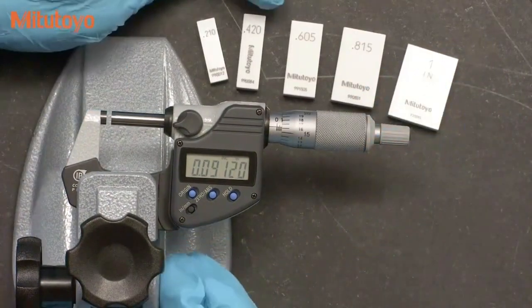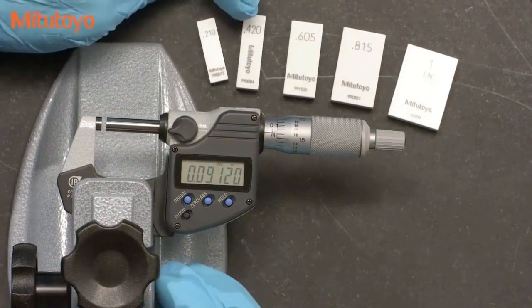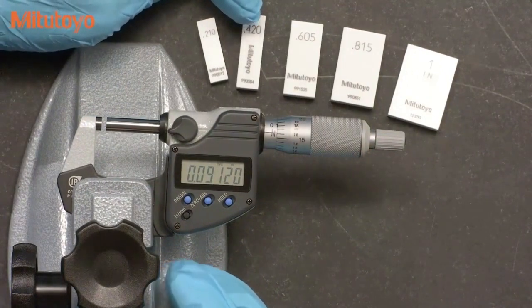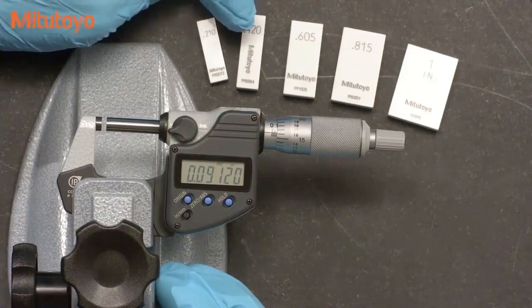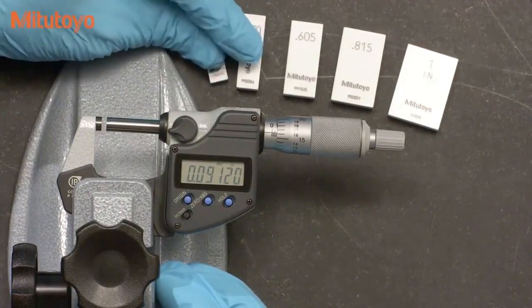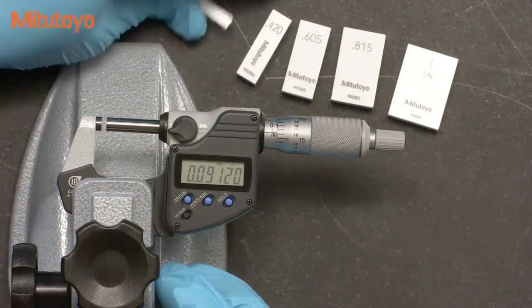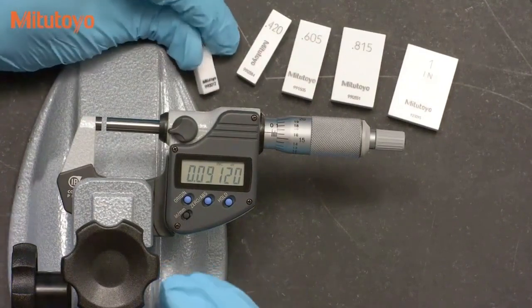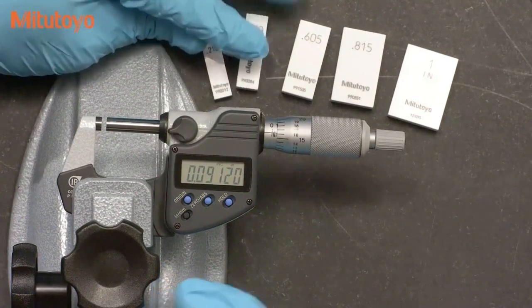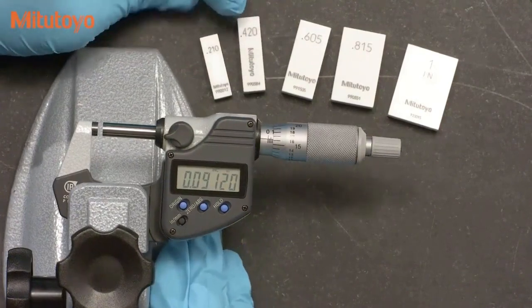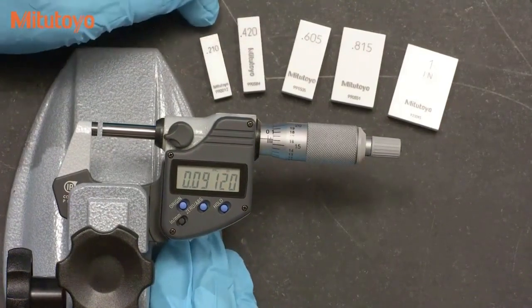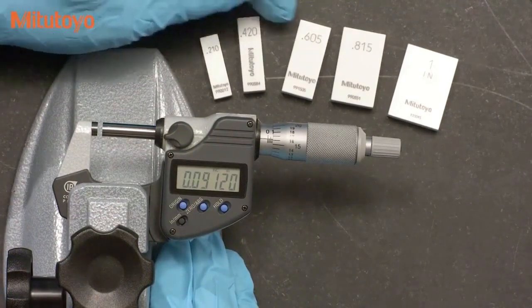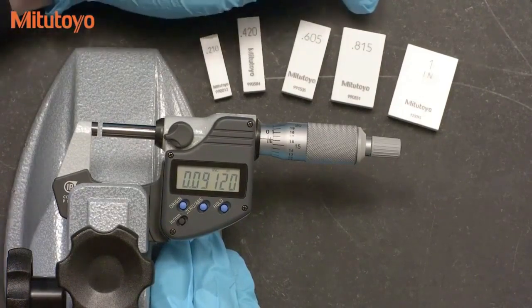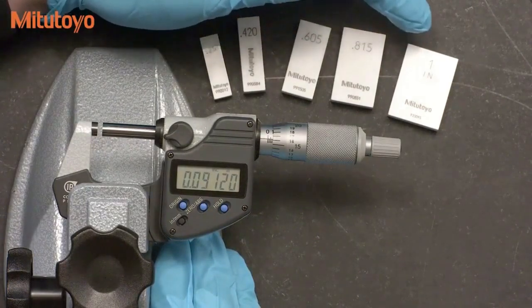We recommend the use of gauge blocks. There really isn't anything better to use, and you need something pretty accurate, so gauge blocks make a good reference standard for calibrating micrometers. The ASME standard recommends 5 specific size gauge blocks for calibration. In inches, these sizes are the 210 block, 420, 605, 815, and 1 inch.